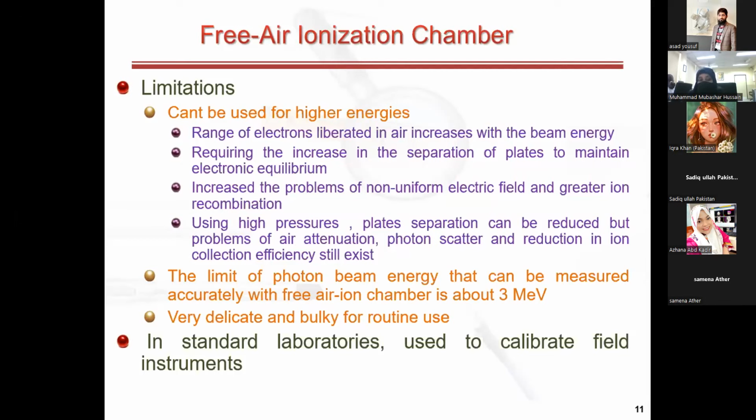But it has some limitations, as already mentioned, that we cannot use it for higher energies. Of course, we can make it possible to use for higher energy, but then the distance between the plates would be very large, which is not practical and would not make it compact. That is why these free air ion chambers are used only in standard laboratories. In these standard laboratories, they are used to calibrate compact chambers that we will see next.